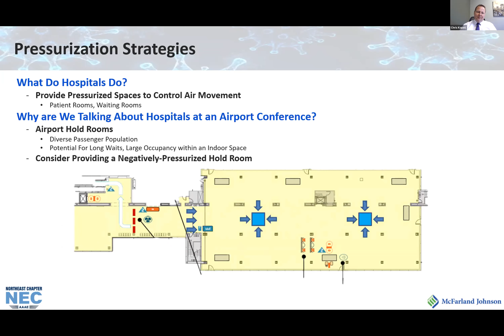I'll pull up a quick example here. We have a small to medium-sized hold room with approximately 6 gates. If we added a couple of exhaust fans here, centrally located, once energized, the exhaust fans would remove the potentially contaminated air from the hold room, keeping the space under a slightly negative pressure, and primarily drawing air from the terminal itself, which essentially contains this area from an airflow perspective.